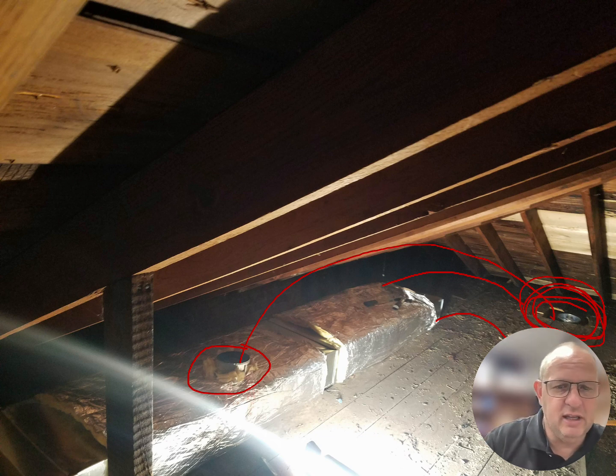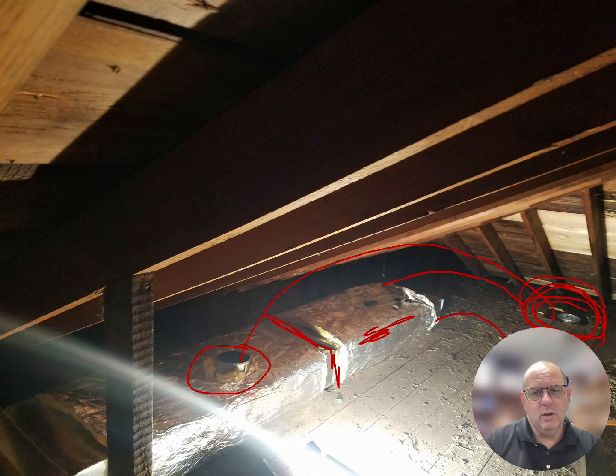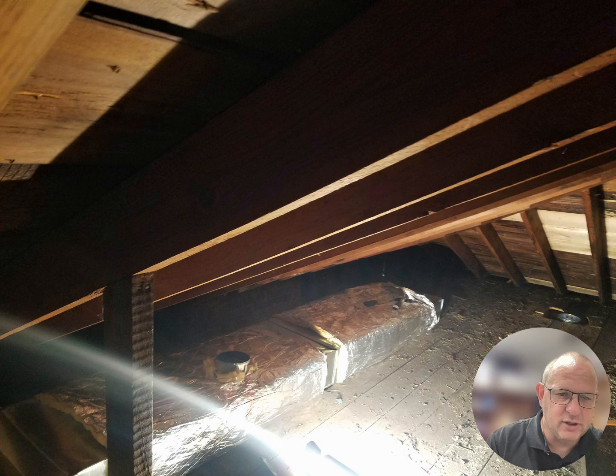You can see the foil insulation that I put around the ductwork, nice and tight, not too loose, not too tight. You can see the gaps that I've left in here, and you're going to have these gaps in there. I'm going to come back through, and I'm going to run foil back insulation underneath that ductwork, and I'm going to put mastic and seal up that ductwork that's on that ductwork right there. Mastic it up so I got a nice tight airtight connection, and then I'm going to put insulation, foil back insulation in there. Do the same process that I just showed you previous. Staple the seam and then tape all the seams up with the foil back insulation that's on there.